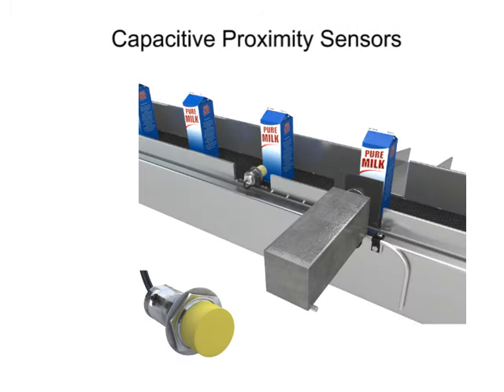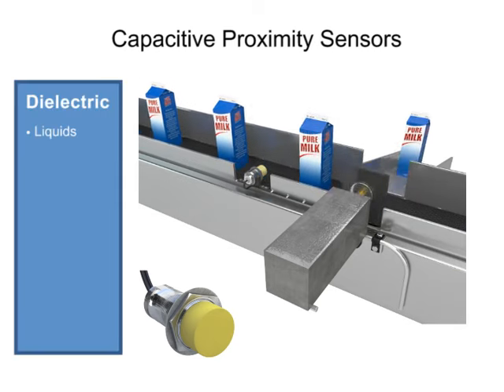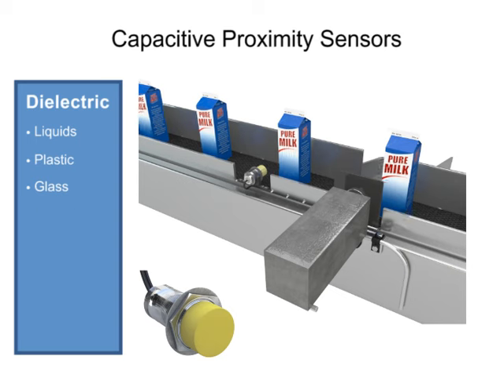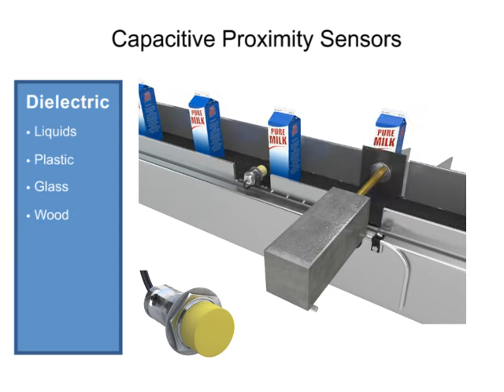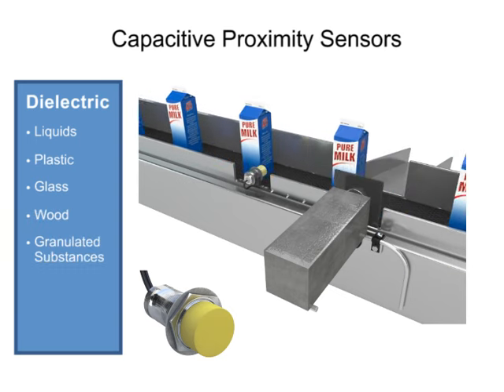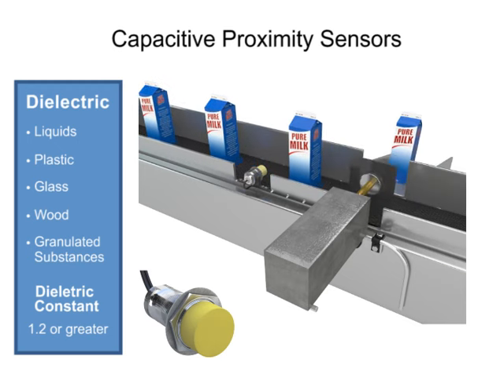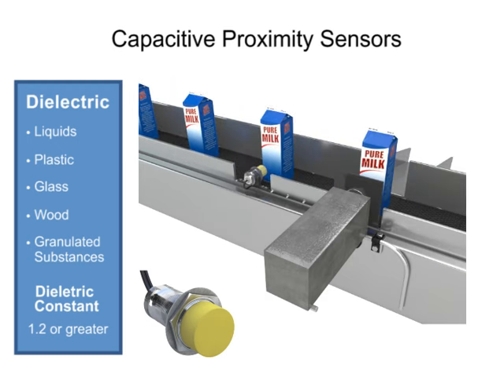Capacitive proximity sensors, on the other hand, can detect dielectric materials such as liquids, plastic, glass, wood, and granulated substances, as long as the material has a dielectric constant of 1.2 or more. Their range is from 3 mm to 15 mm depending on the dielectric material to be detected.